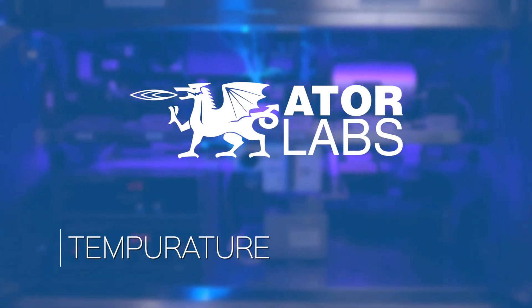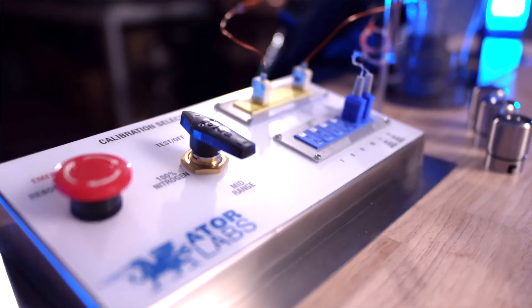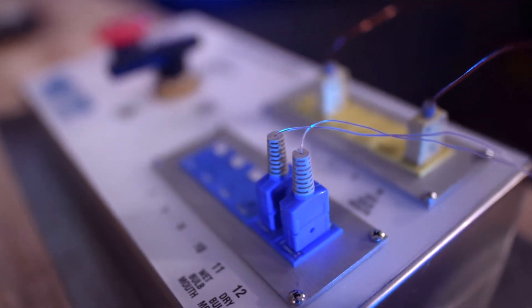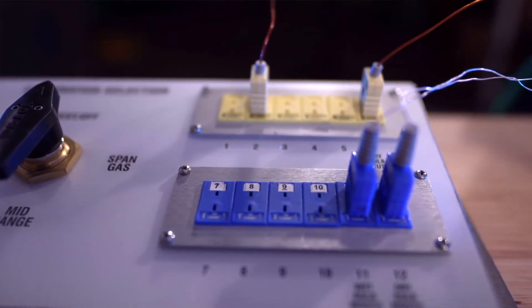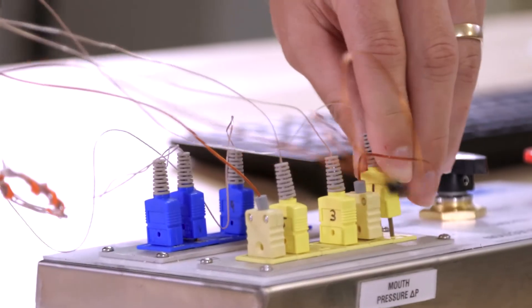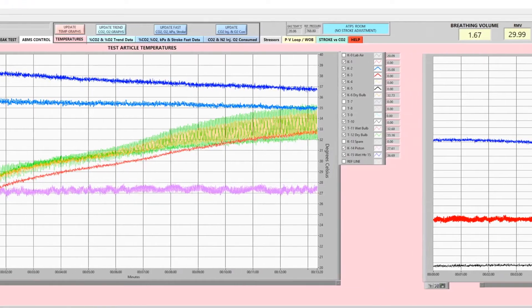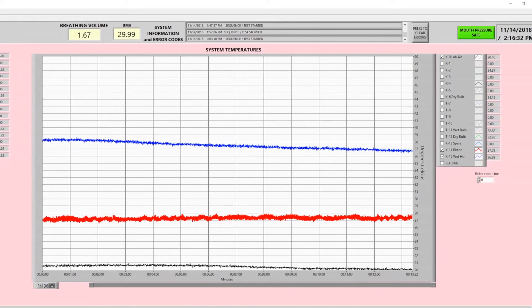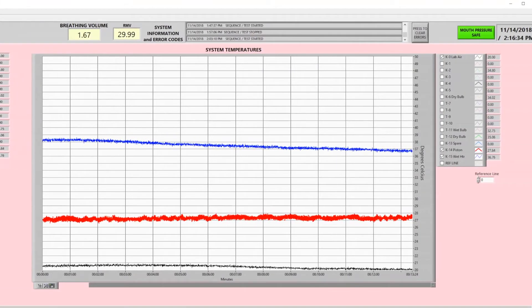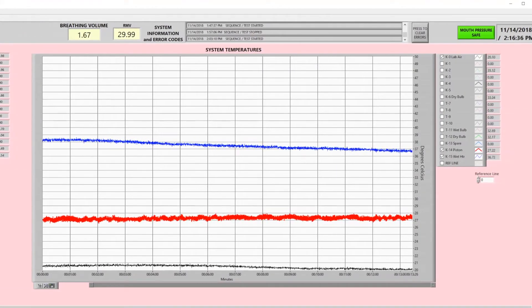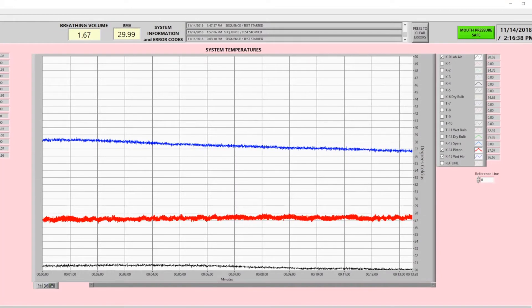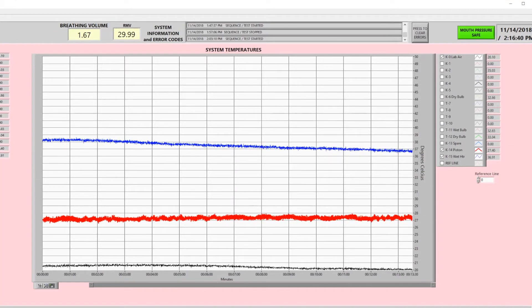In this video segment, we're going to review some of the temperature evaluating capabilities of our system. Here on the panel, we have an additional set of temperature probes that the user might wish to plug in to investigate some temperature changes within the apparatus under test. The system has several of its own monitoring temp probes. Here on the right screen, we track the system temperatures, the wet heater, the mouth temperature, and the room in which we are testing.